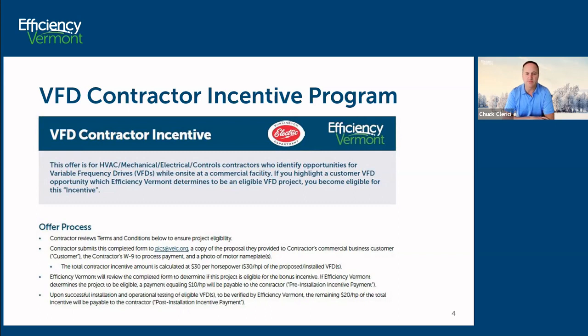So we're trying to use this program opportunity to make sure that the VFDs that are installed are properly tuned to deliver energy savings. A VFD is a sort of box of electrical components. It draws power. So if you were to put a VFD on a motor load and just let it sit at 60 hertz, you would actually be adding energy to the load that it's controlling. It's approximately 3% of the load that it's connected to.